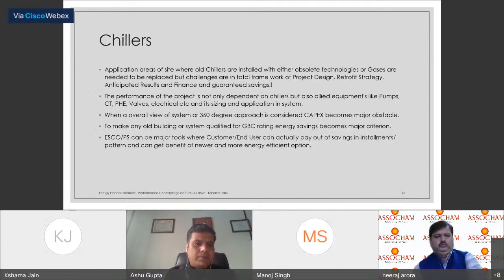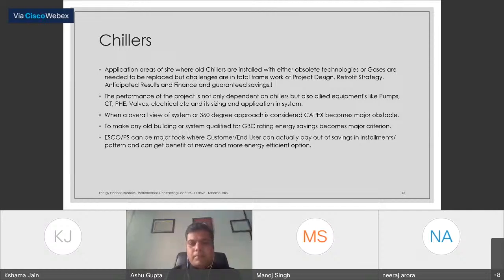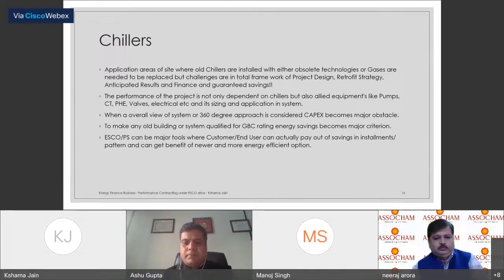When we talk about chillers, the application areas are sites where old chillers are installed with obsolete technology or obsolete refrigerant gases that need to be replaced. Challenges lie in the total framework of project design, retrofit strategies, anticipated results, finance, and guaranteed savings. Under the ESCO module, we audit the total project and look at allied equipment like pumps, cooling towers, PHEs, and electricals, ensuring their sizing is appropriately made so that energy efficiency goals are achieved.